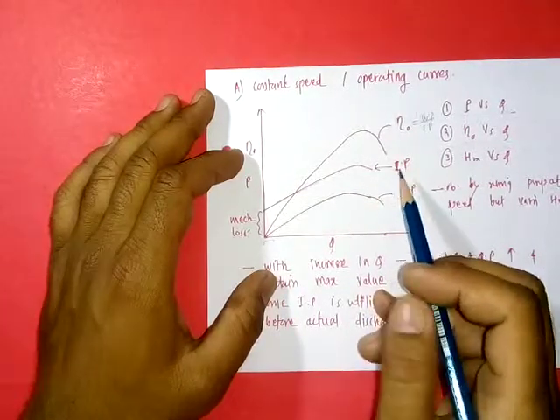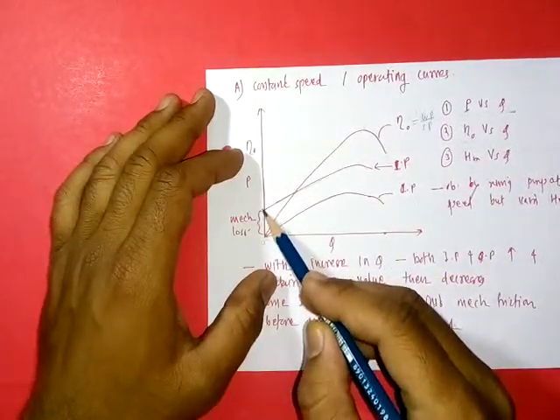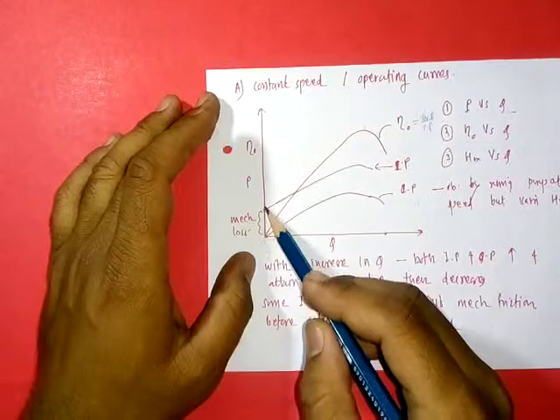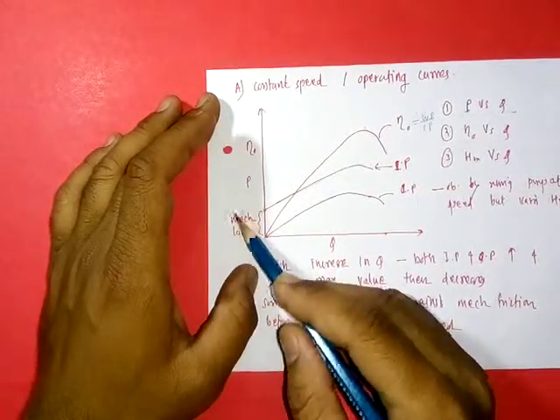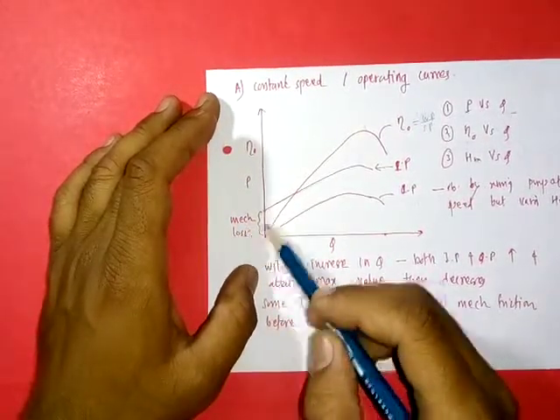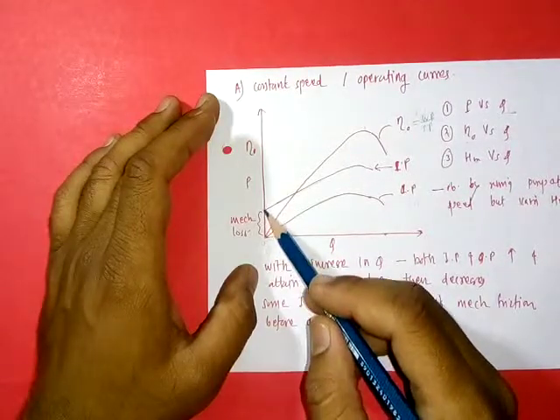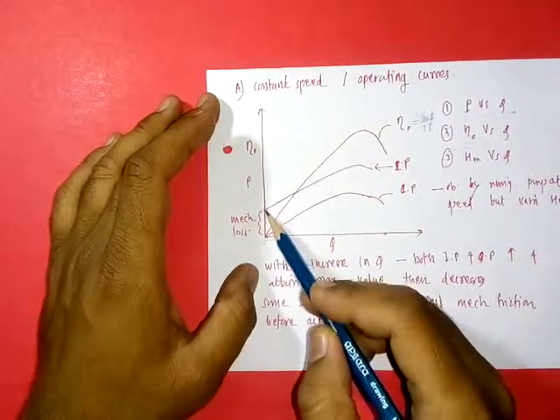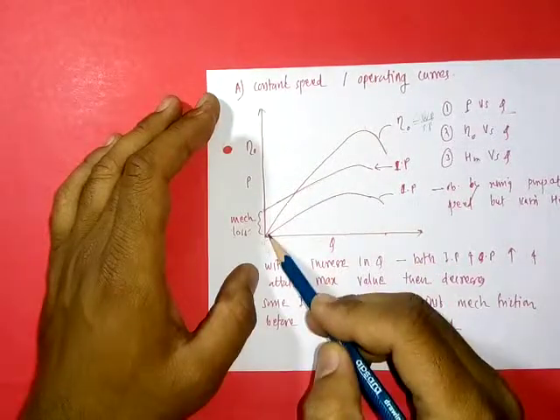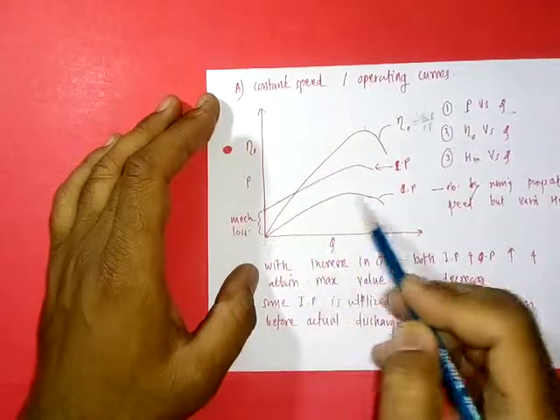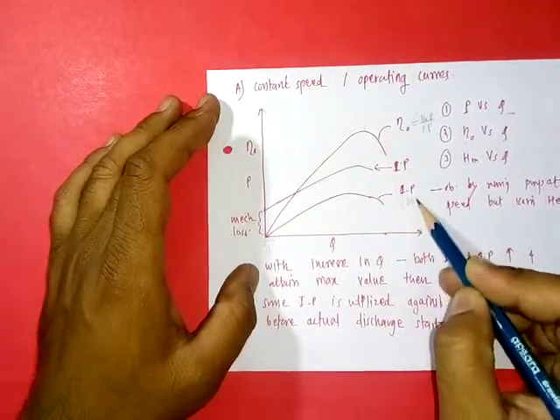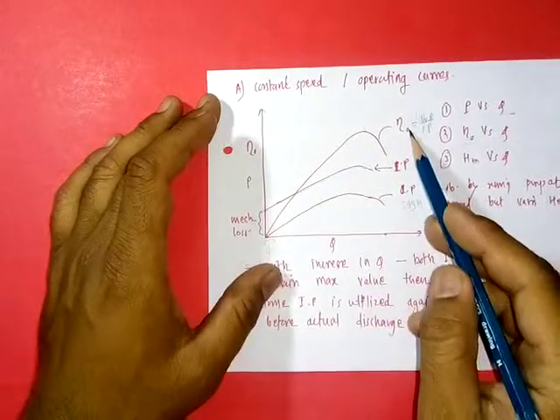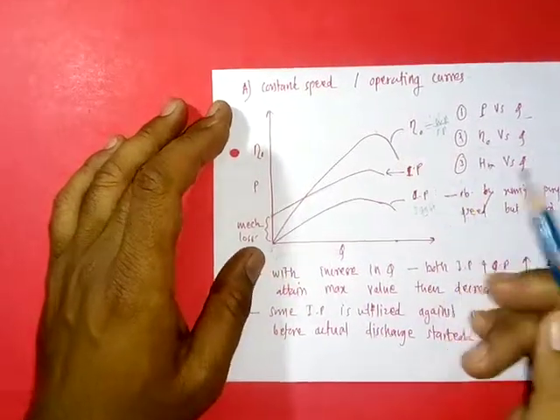This initial input power at zero discharge is utilized against mechanical losses within the pump. After the pump overcomes those mechanical losses, with increasing input power, discharge starts. With starting discharge we get output power, which is the water power at the outlet, and once output power is nonzero, the overall efficiency begins.